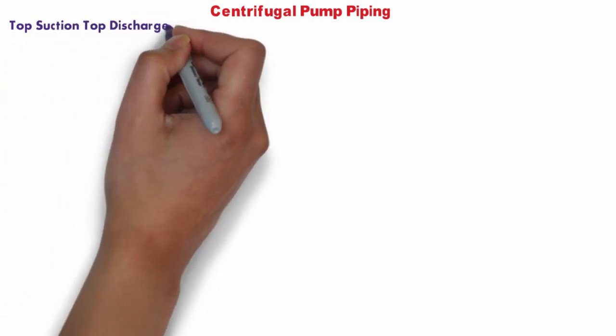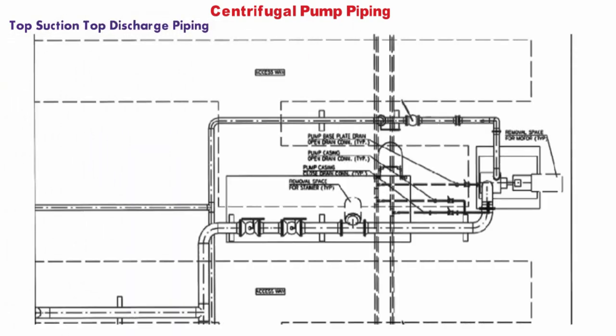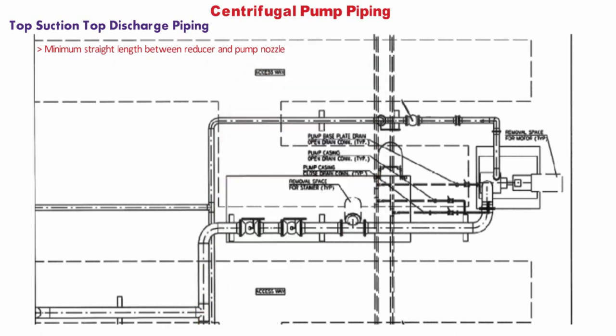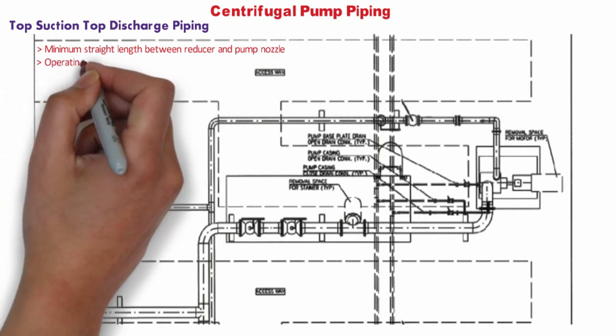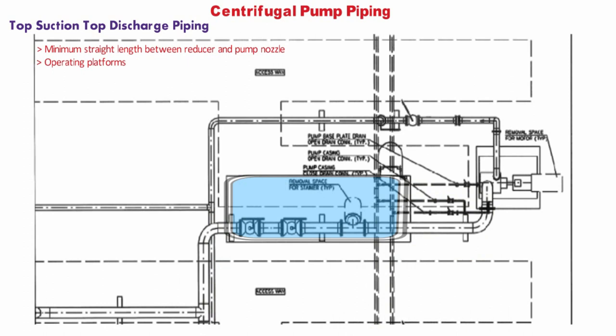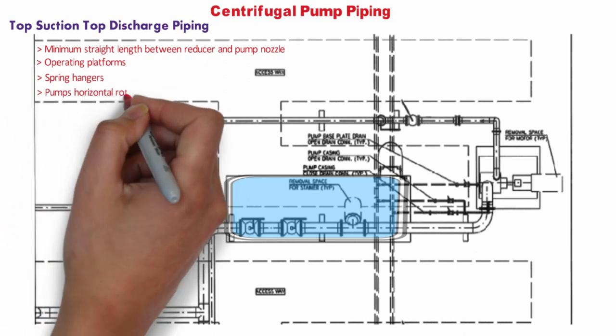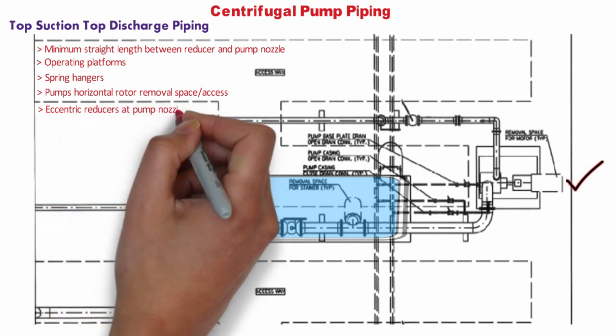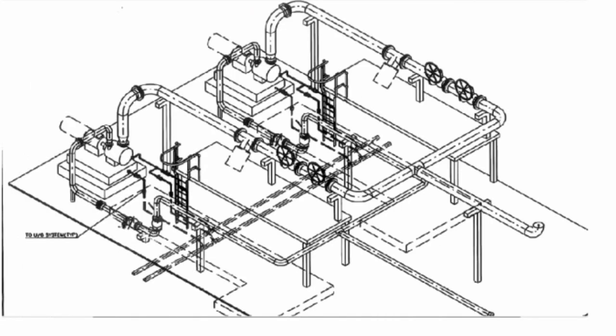For top suction and top discharge pumps, minimum straight length between the reducer and pump nozzle must be confirmed from process, pump vendor, or project requirement. A removable spool piece for pump removal should be provided, along with an operating platform if needed to access block valves and strainer. A spring hanger, if required by the stress engineer, should be provided as close as possible to the elbow to manage dead weight and thermal expansion. For higher line sizes, eccentric reducers at the pump nozzle can be considered when line sizes are much larger compared to pump nozzle sizes.